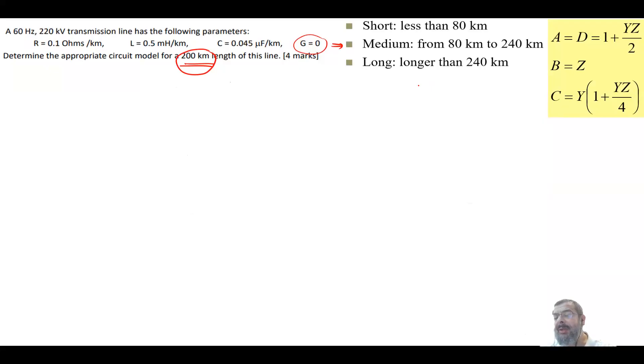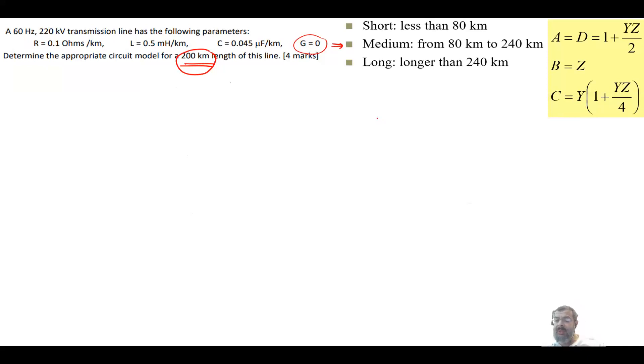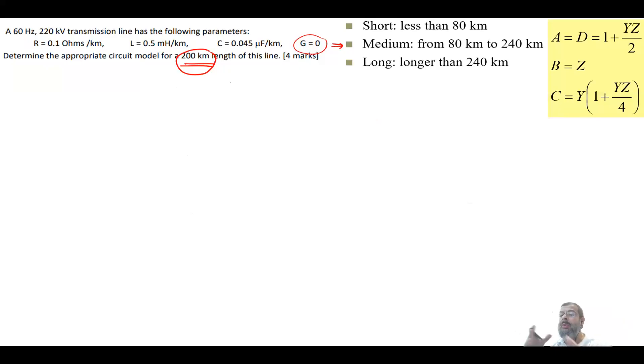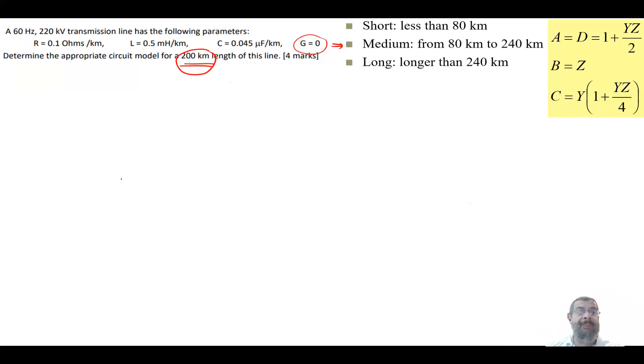For the medium model, the ABCD parameters are: A = D = 1 + YZ/2, B = Z, and C follows its own formula. We'll use this model to calculate the sending-end voltage and current. To do that, we first need to find Z and Y, incorporating the line length since the parameters are given per unit length.